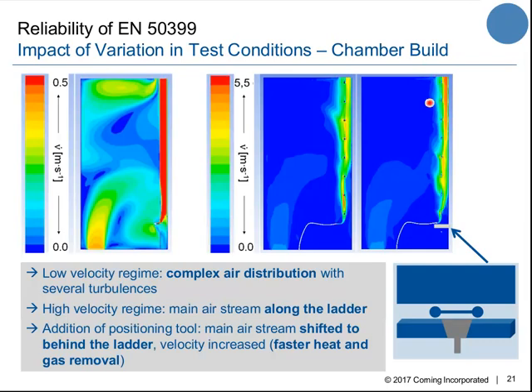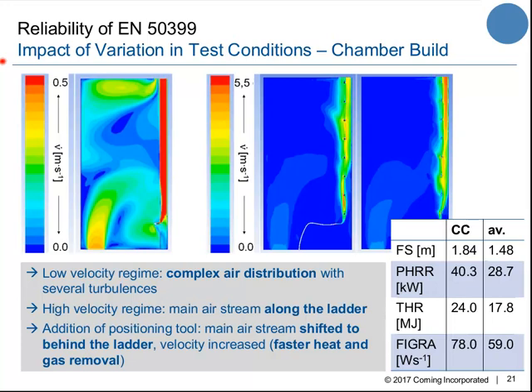So, of course, we were wondering how this impacts the flame spread. So we tested this. We installed this kind of baffles in our chamber. And what you see here is now an average number. That means we tried out many different designs of baffles. And one has really to say, the flame spread changes strongly depending on the design of the baffle. This is now just an average number to give you an idea that baffles or additional installations do not only change air distribution, they really change also the flame spread. Again, how much they change it depends on the design and the solution that is implemented in this chamber.